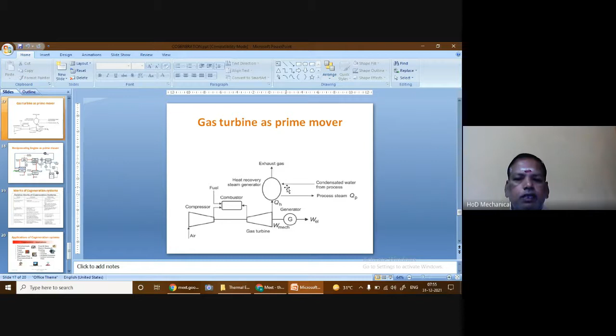That mechanical energy is converted into electrical energy by connecting the generator to it. Then the hot gases leaving the turbine are taken into the heat recovery steam generator, where water is supplied and gets heated up, and because of that steam is produced. That steam is used for some processing applications, and then the condensed water from the process is circulated again into the heat recovery steam generator for further extraction of heat. After losing the heat to the water, the gases are let into the ambient. So this is the gas turbine as a prime mover.